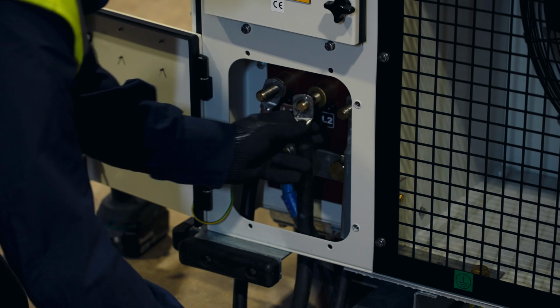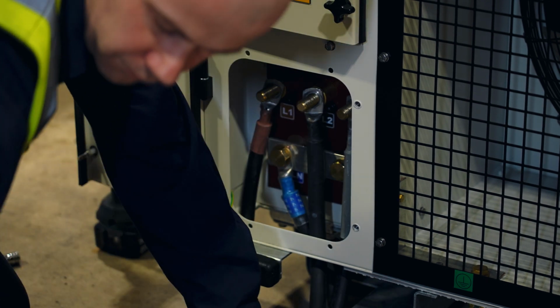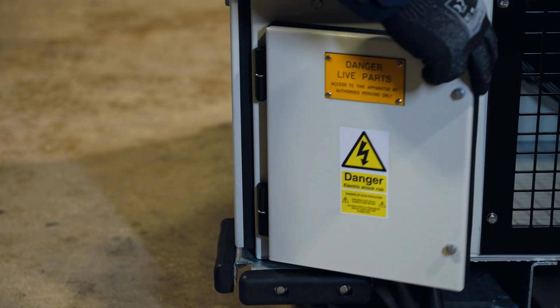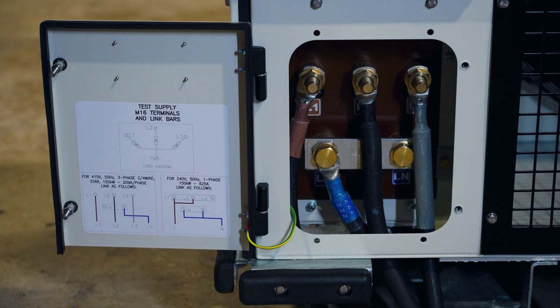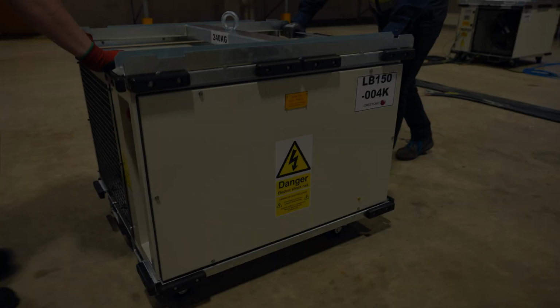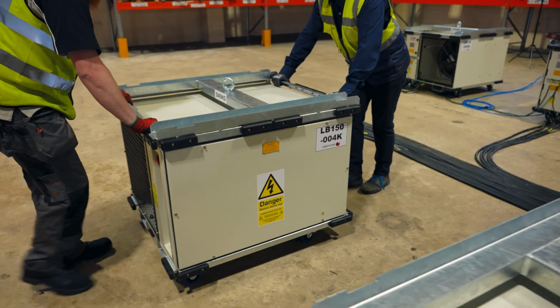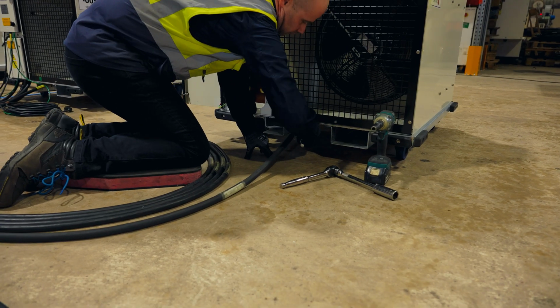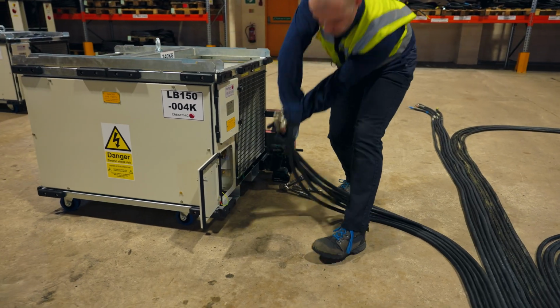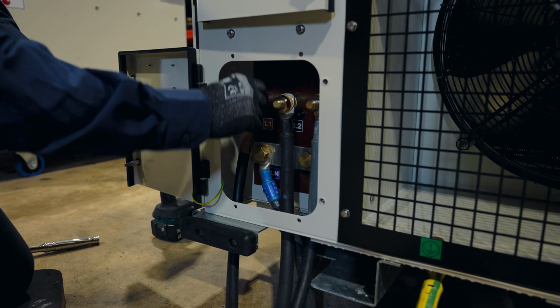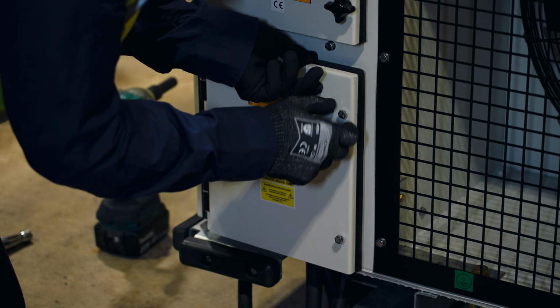It is possible to use the load banks in both 3-phase to a maximum of 415 volts or single phase to a maximum of 240 volts. Full capacity of 150 kilowatts is possible in both modes. When connecting the load cables to the load banks, an earth cable must always be connected to the load banks. These cables should be rated adequately for the load required, ideally being rated for the full capacity of the load banks.